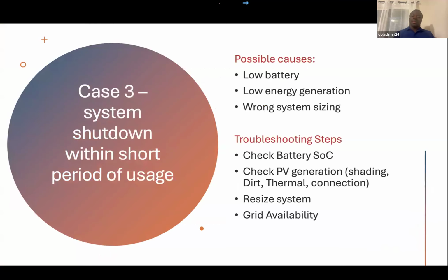Case number 3, system shutting down within a short period of usage. Your client is complaining that the system just shuts down. They use it for 1 hour, 2 hours, and it's shutting down. Maybe because of low battery, low energy generation, or wrong system sizing. So how do you troubleshoot for this? You check your battery state of charge. Is the battery well charged?